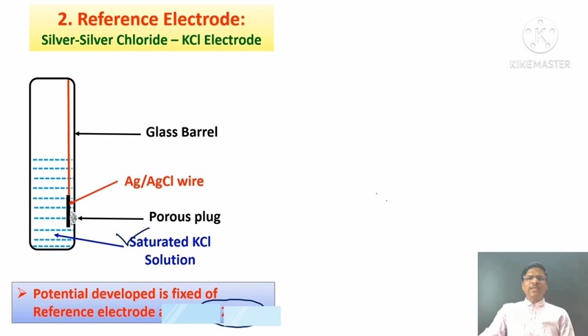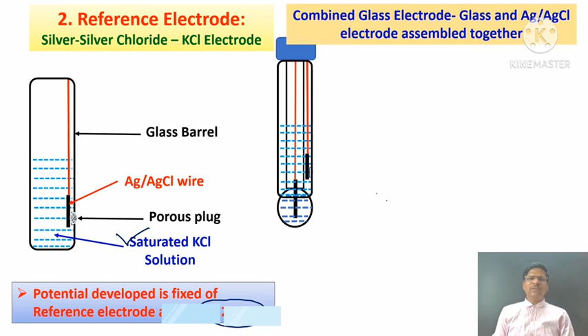The potential developed on the reference electrode is fixed. The sensor is made up of the working electrode, the glass electrode, and the reference electrode, the silver chloride electrode. When these two electrodes are combined together, we get the combined glass electrode or the pH sensor. The glass electrode is fitted with the reference electrode, and thus we get a cell. The pH sensor, or the combined glass electrode, is a cell. In the cell, the glass electrode is one electrode, and silver chloride is the other electrode.